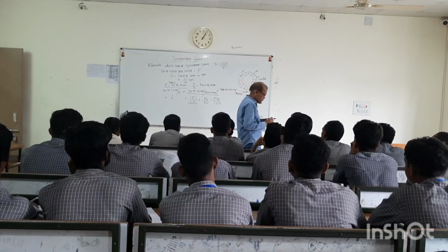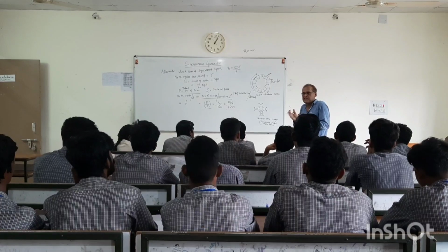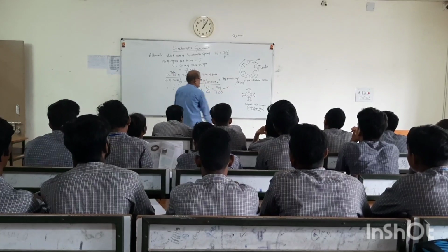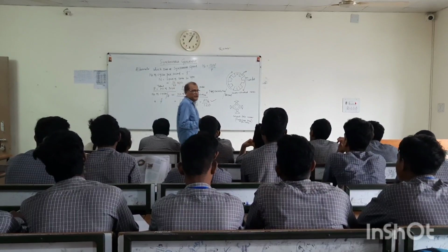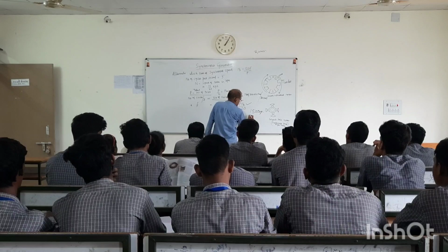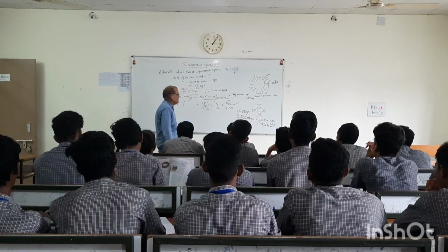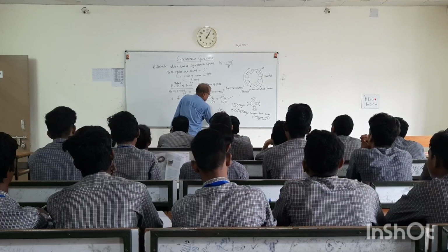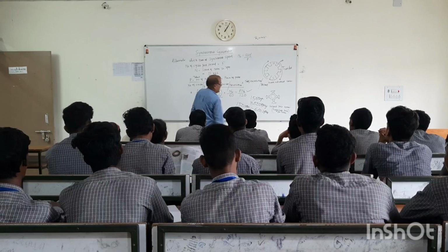In an actual power plant, the alternator is driven at a specific speed, that is Ns, the speed of the rotor. If it is steam driven, that is 1500 rpm or 3000 rpm. In case of hydro power driven, that is 150 rpm to a maximum of 600 rpm.